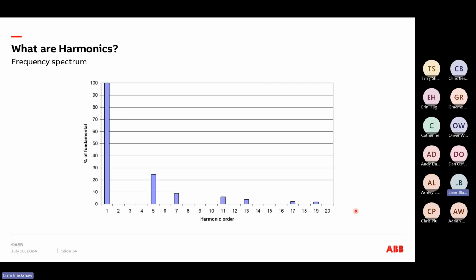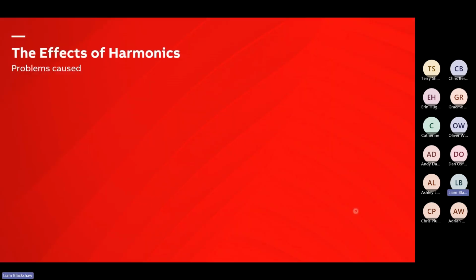And it's always worth looking at things like percentages, the percentage of the fundamental. When you look at this as an example, it's like, well, great, what does that mean to me? Okay, it tells you for a particular harmonic order what level of current or voltage I'm getting. It could be in the milliamps, could be a lot less than that. But it's those standards or regulations that tell us that at a particular order, our harmonics on a particular part of the system need to be at this level given certain criteria. Which probably moves us on nicely to the effects of harmonics, the problems that are caused when we have harmonics on our system.